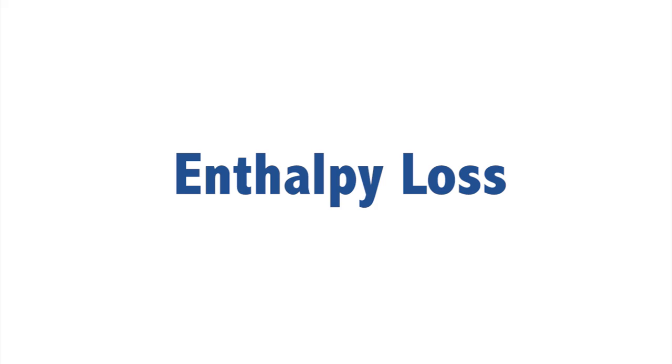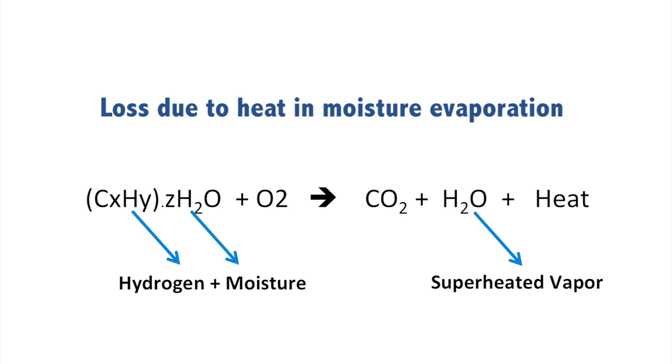Now we come to the third kind of loss, which is the enthalpy loss. Hydrogen is an integral part of almost every kind of fuel. When this hydrogen in the fuel combines with the oxygen present in the combustion air, it forms H₂O. This H₂O uses the heat generated in combustion to vaporize itself. Additionally, there is some amount of moisture present in the fuel, which enters the combustion process in liquid form and goes out of the stack along with the flue gases in vapor form. The heat used by the H₂O to vaporize itself and exit via the stack at the temperature of the flue gases is basically the enthalpy loss.